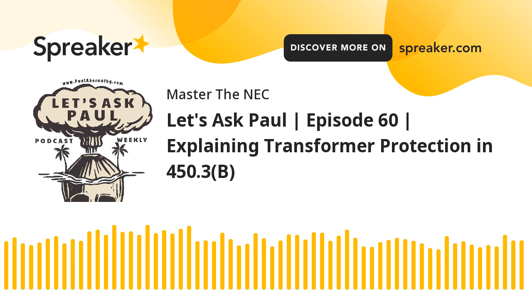All right, so the ampacity of those conductors, if you look at 240.21(C)(2), I'm going to read it to you. It says, transformer secondary conductors not over 10 feet long. If the length of the secondary conductors does not exceed 10 feet, and that is 10 feet from the point that it leaves the transformer up to the termination into the overcurrent device, let's say in a panel, or to a piece of equipment that has the amp ratings on that equipment, then I'm going to follow these rules for the conductor sizes. And here's what it says.